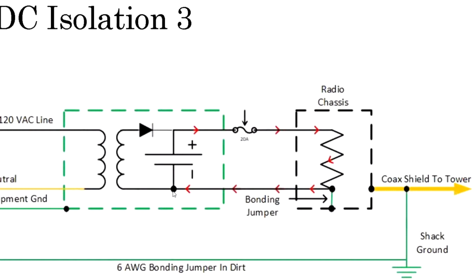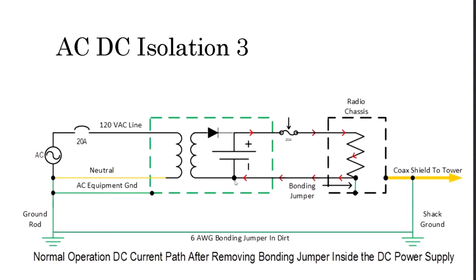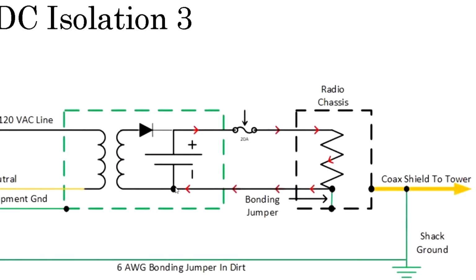There's absolutely no reason for that bonding jumper to be in there. Okay, there's no code or equipment requirements that require that jumper to be in there. It doesn't serve any purpose. It's a troublemaker. So we can get in there and take it out. And now then, we have AC and DC isolation. Under normal operations, note what's happening. Current leaves the DC power supply, comes through our radio, and every bit of it returns straight to the power supply, back on the DC negative conductor. Exactly what you think and the way you think it should work and how it should work. Okay? Pretty simple. What about a fault?